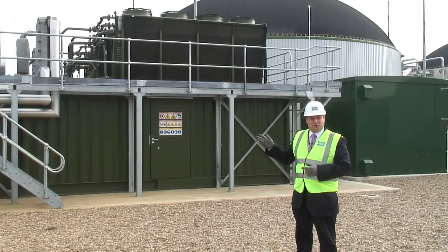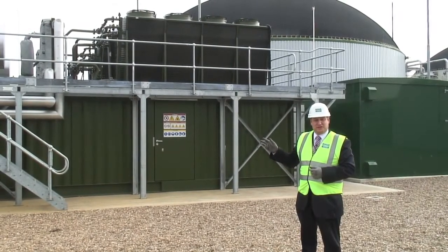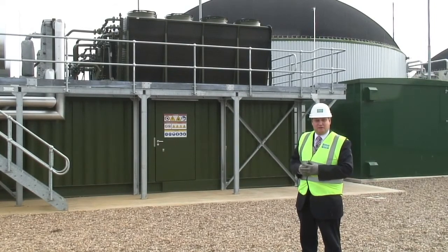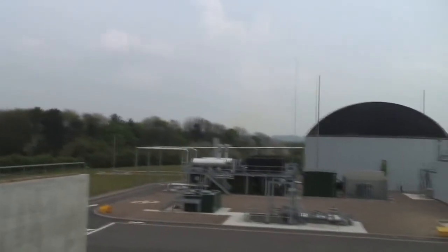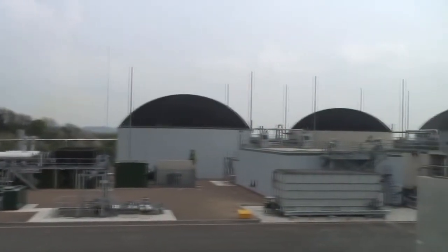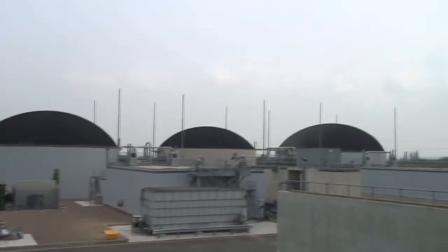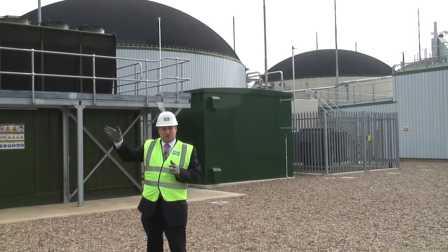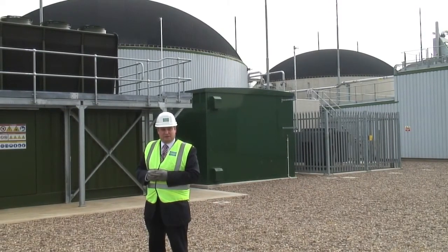The biogas stored in the domes of the secondary digesters is fed through the overhead gas pipework to feed two 1 megawatt CHP containerised generating sets. These produce electricity at about 400 volts, and then through the switchgear and transformers, it's uprated to 11 kV and exported across into the site ring main which feeds the sewage treatment works.